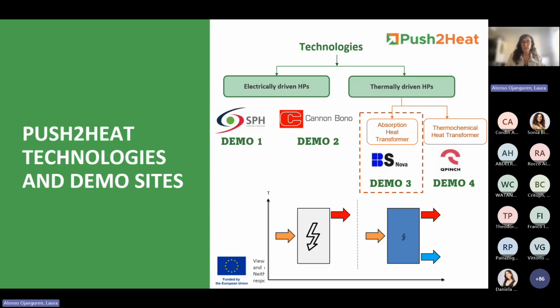The waste heat comes at a medium temperature level, and approximately half of the heat that is coming at a medium temperature level can be upgraded to a higher temperature level, and the rest of the heat needs to be rejected or dissipated at a lower temperature level. And when you compare this with the compression heat pumps, you have a minor electricity consumption, just a little bit of electricity consumption for internal pumping in the system, because this is mainly thermally driven by the waste heat. And now I will focus on demo 3.